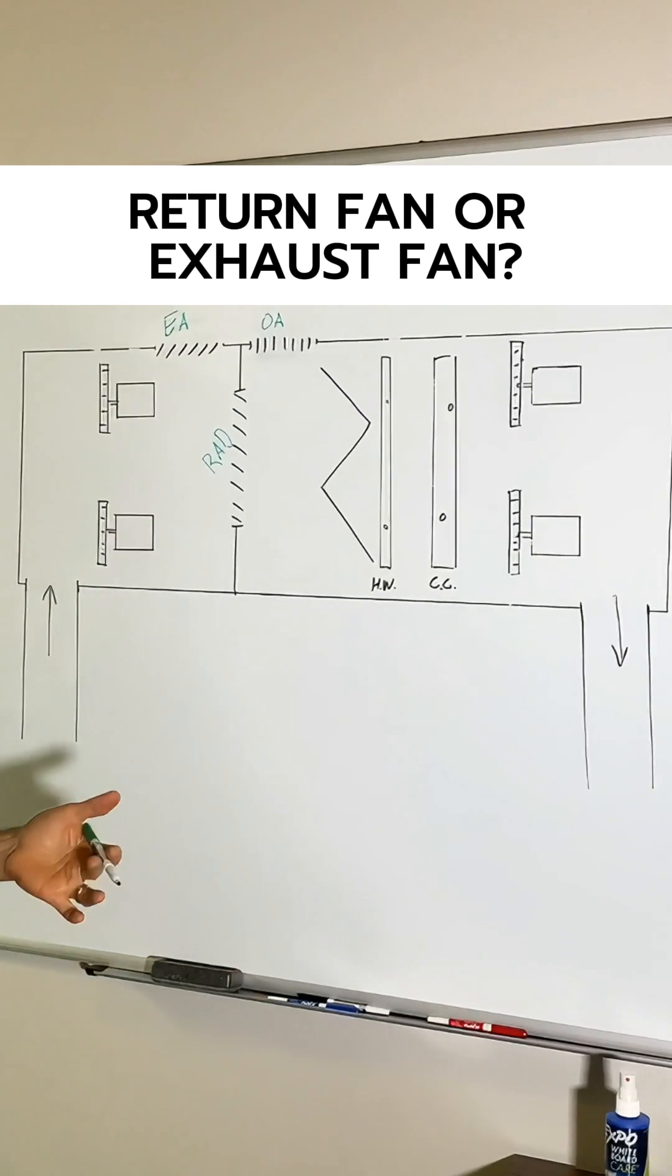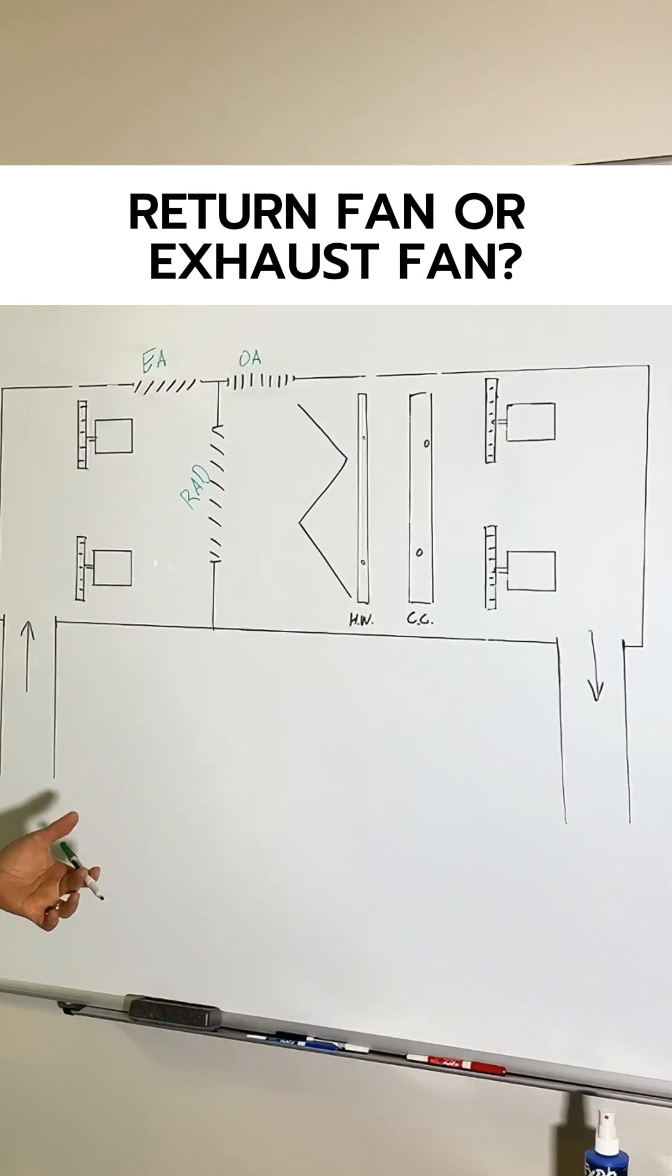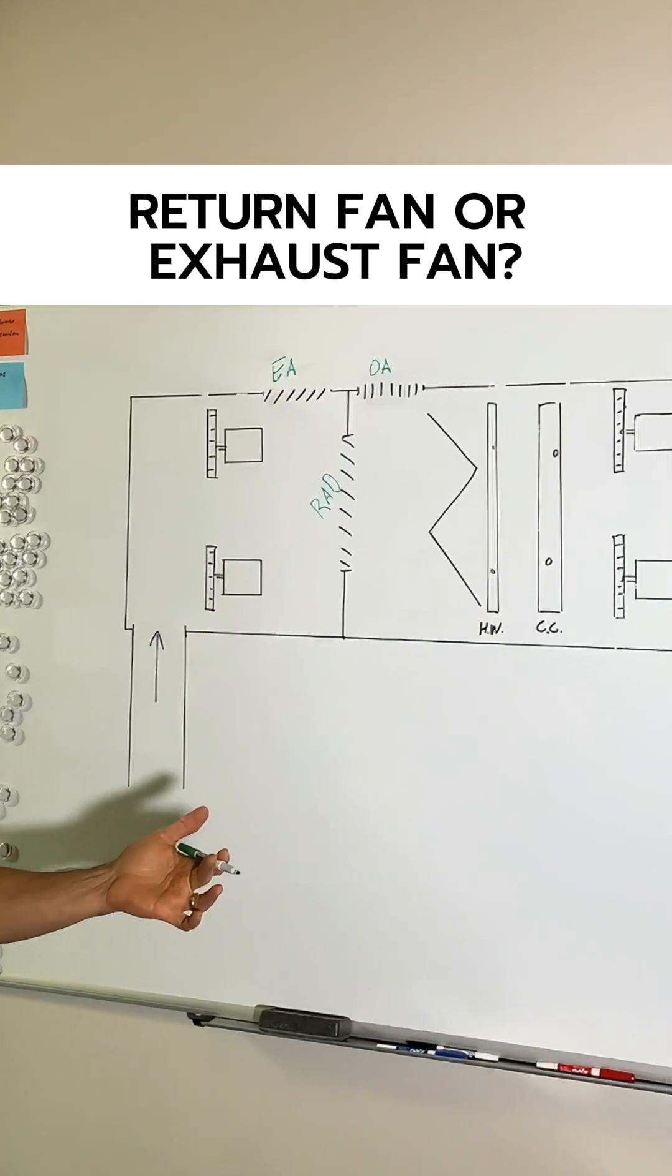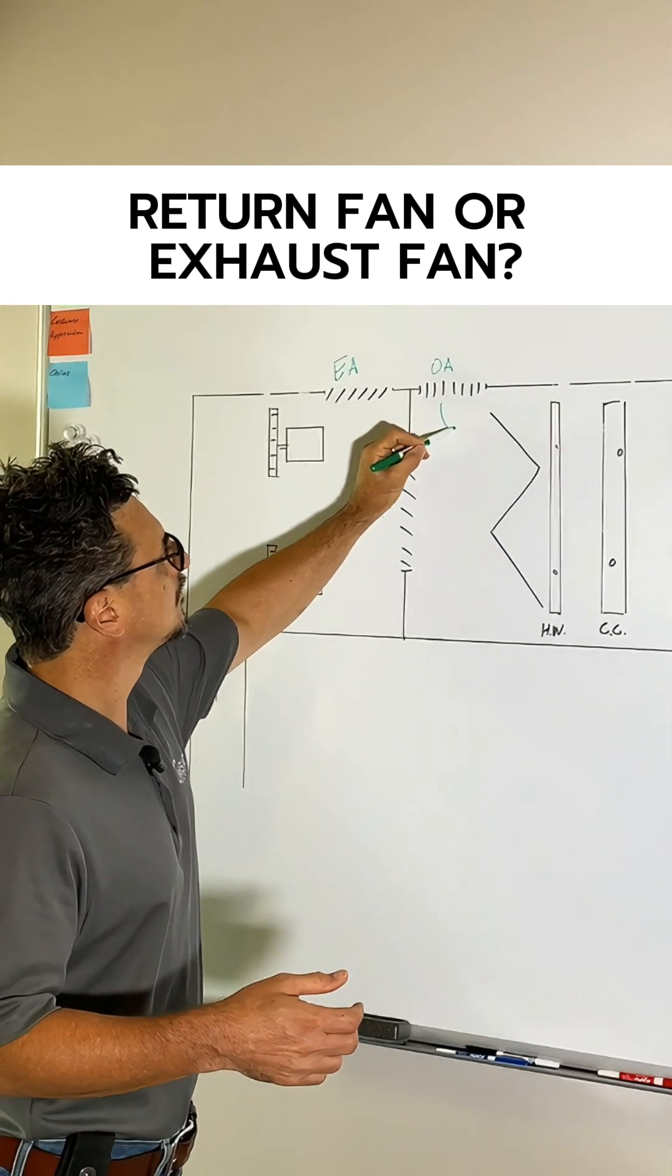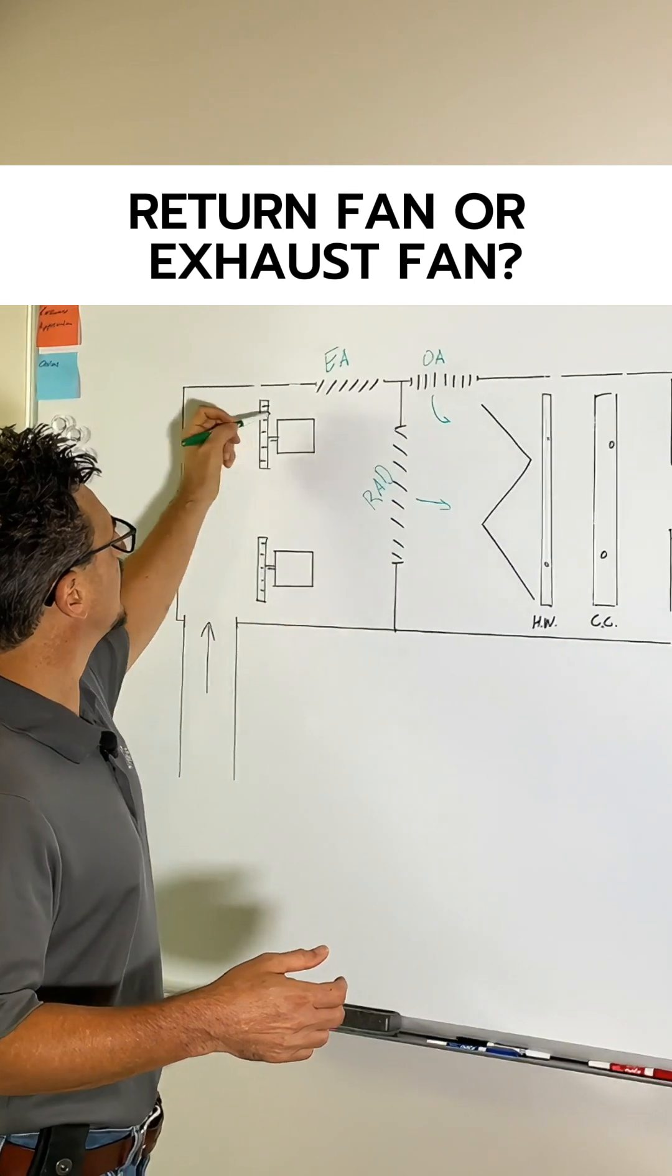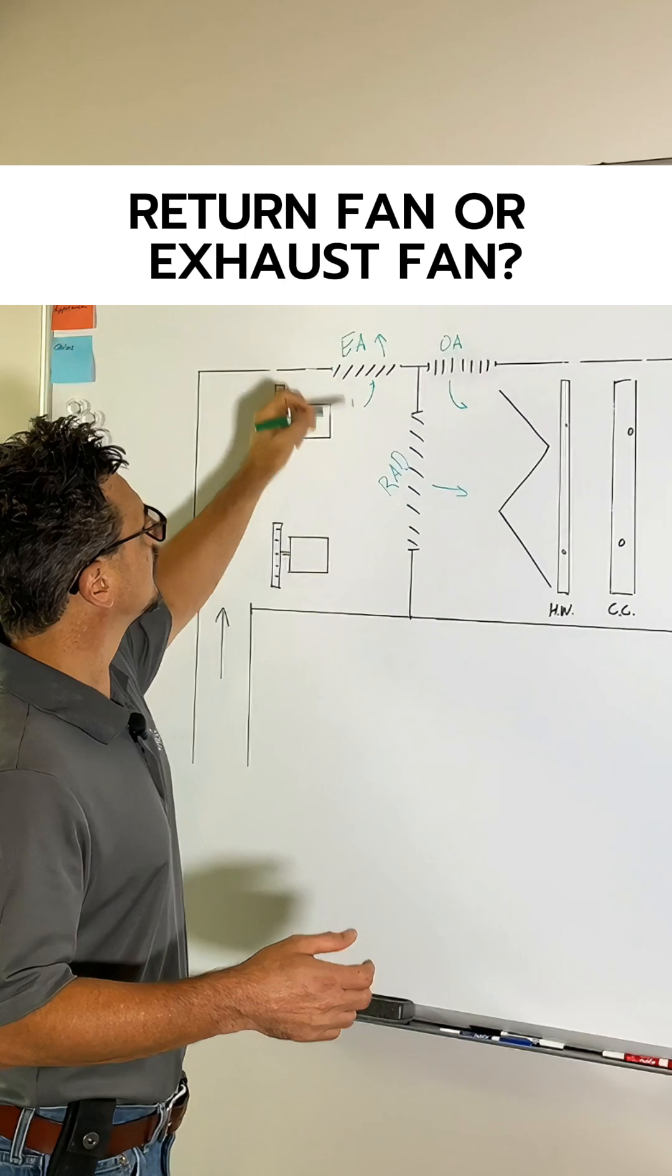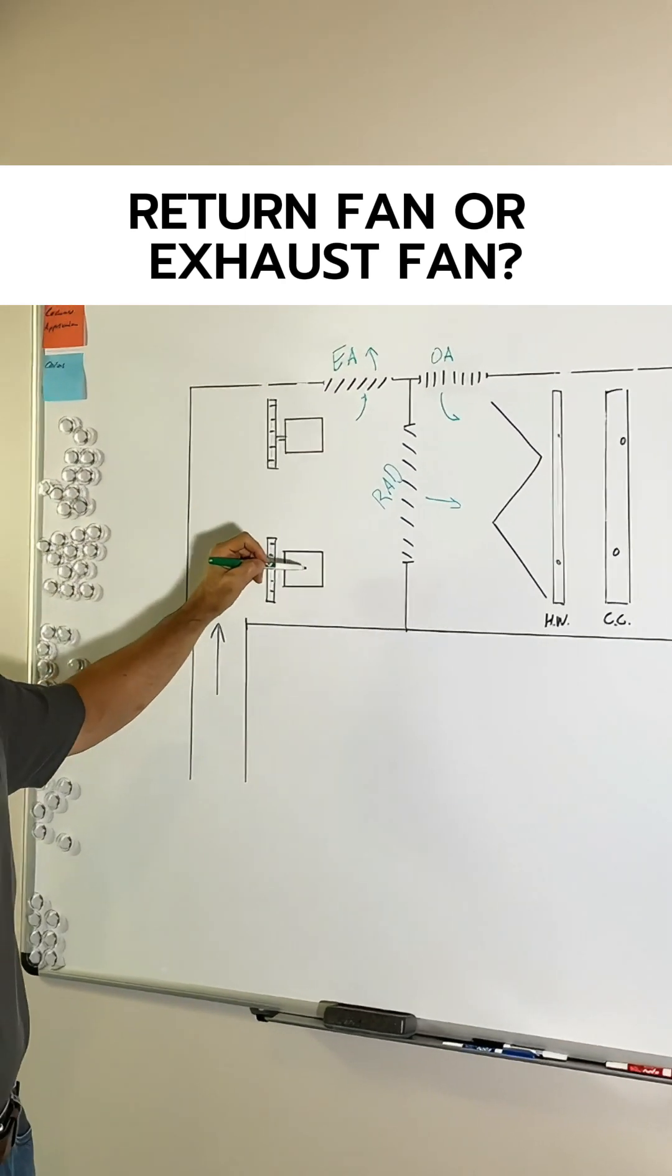So this is what is called a typical return air economizer, 100% economizer arrangement. So what happens is in general operation, let's say you have 20% outside air. Your outside air is coming in here, mixing with your return air, and your exhaust air is going out here.